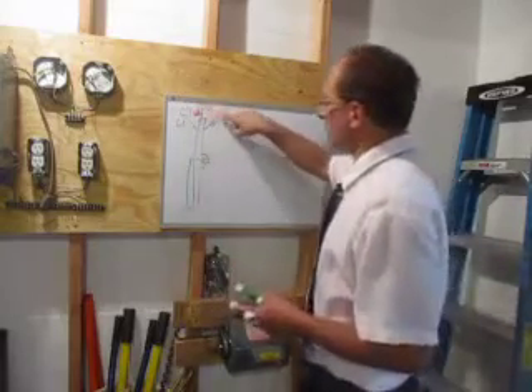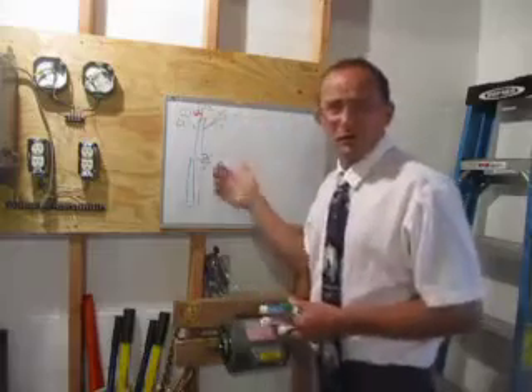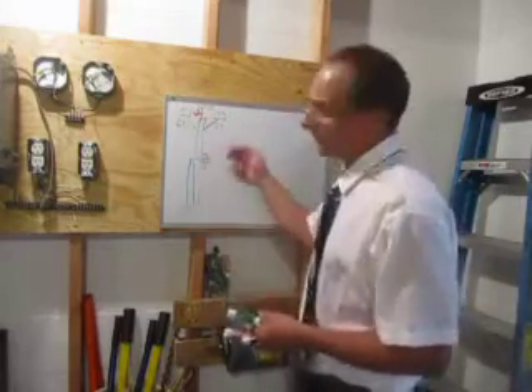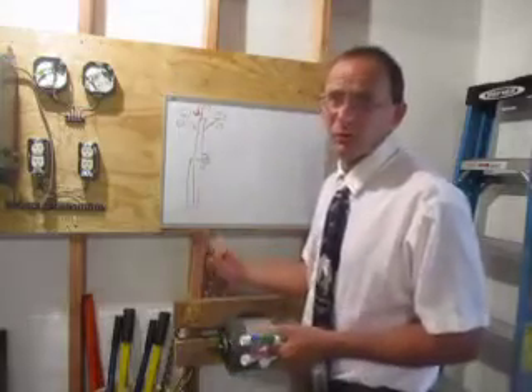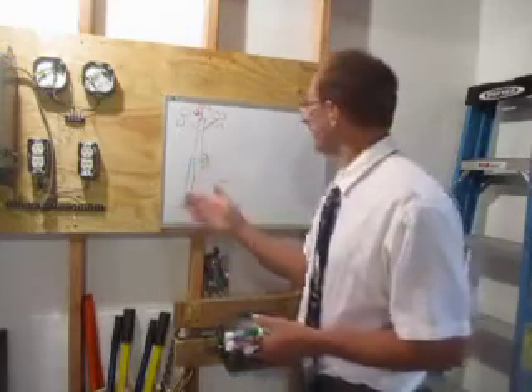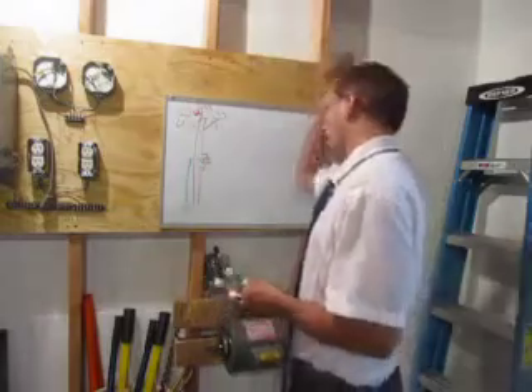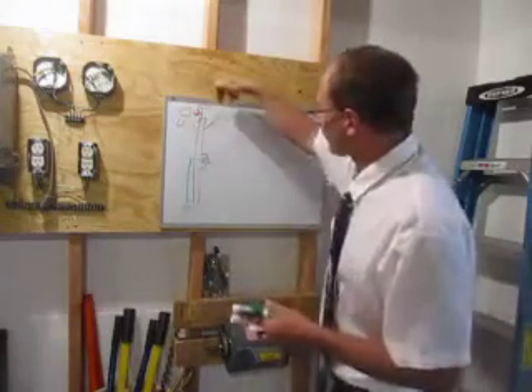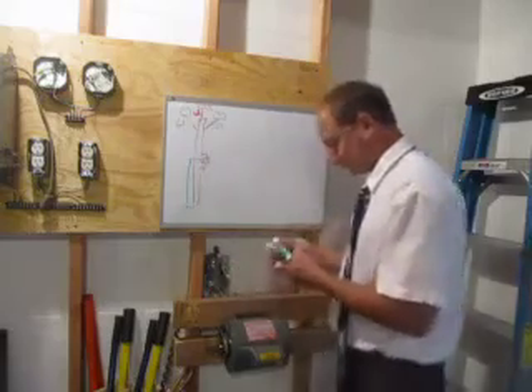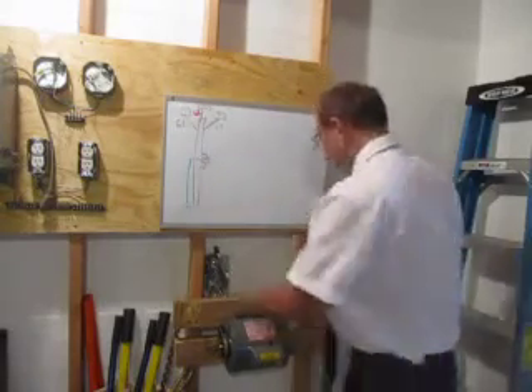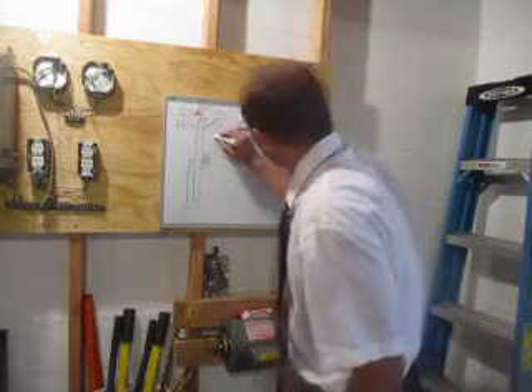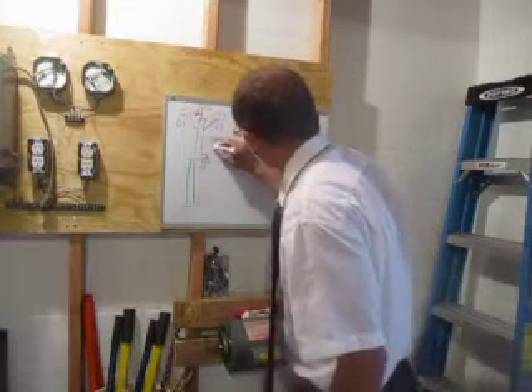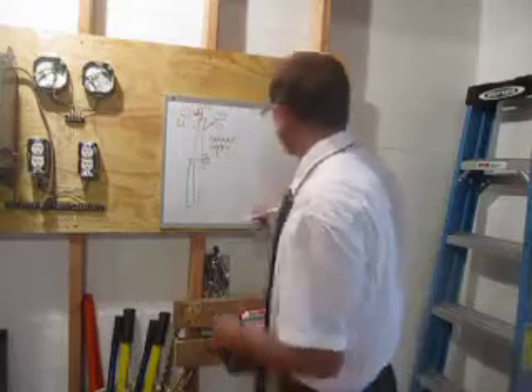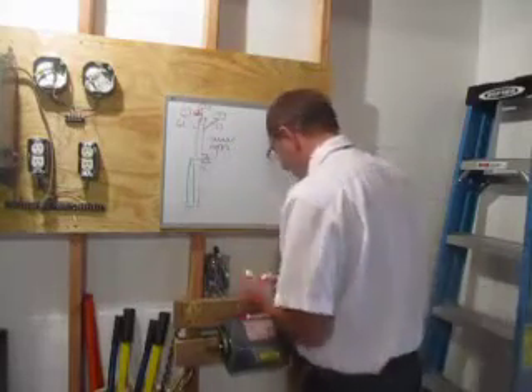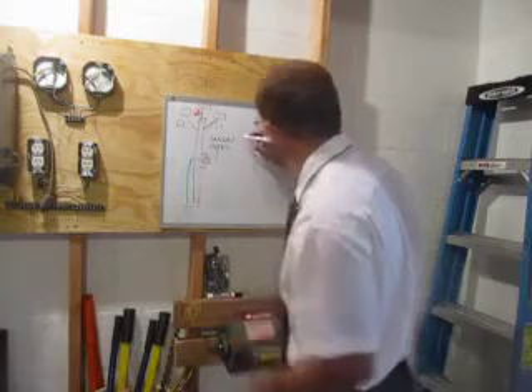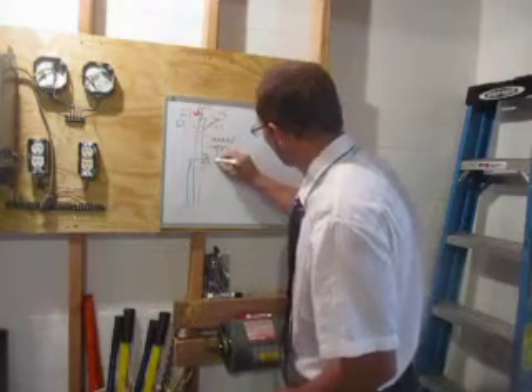But if you grab any two of these three, any pair of these three up here, you got 12,470 volts. Basically, take your single phase voltage, 7200, times the square root of 3, which is 1.73, and that'll give you your three phase voltage for that. So 12,470 three phase, 7200 volts to ground. Then when you get a transformer, you put a transformer on the pole. You got your high voltage and your center tapped low voltage. Take your transformer, ground this, take it to neutral.